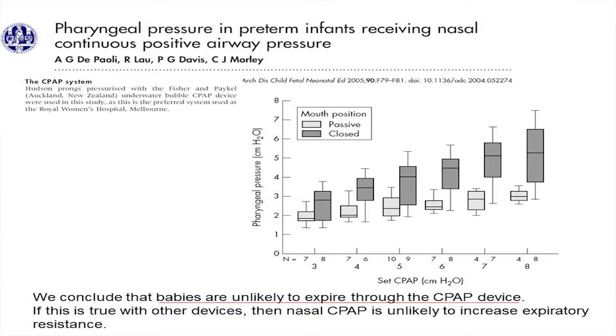And you can see that closed it's higher than passive, so when the mouth is open you even have a very low CPAP pressure. But if you have the mouth closed, you reach an average of 5 centimeters of water instead of the set 8. And they never observed an increase of CPAP pressure during expiration. Because if the baby would breathe out through the nose, with the mouth closed, you should see an increase of CPAP pressure. You should see an increase in flow. And they didn't observe it. So that made them conclude that babies are unlikely to expire through the CPAP device. They expire through the mouth.